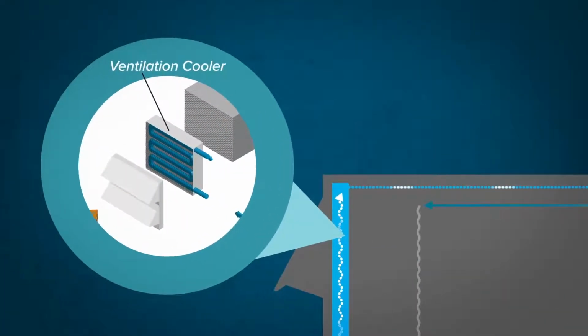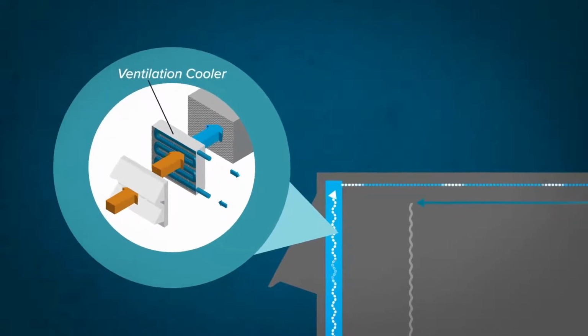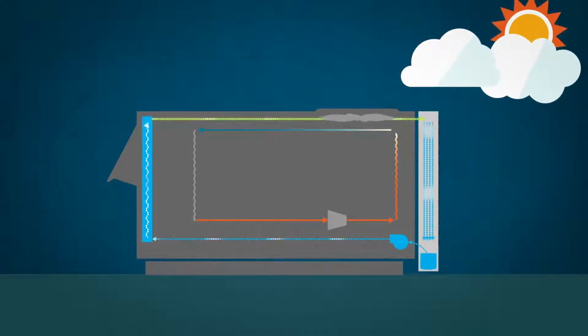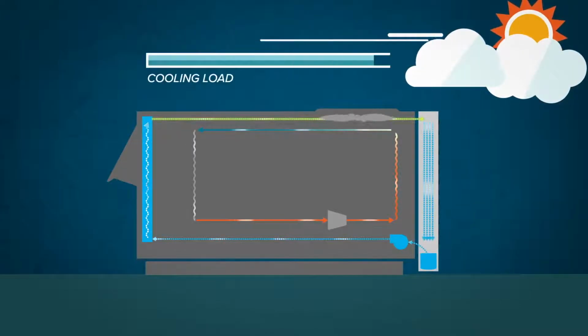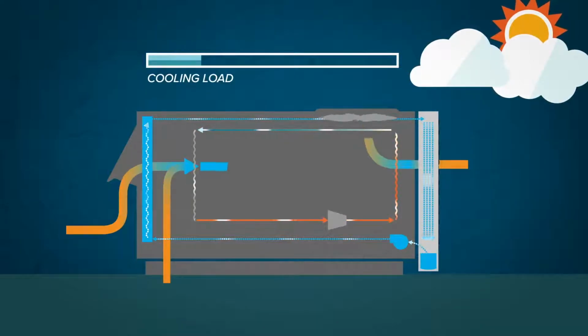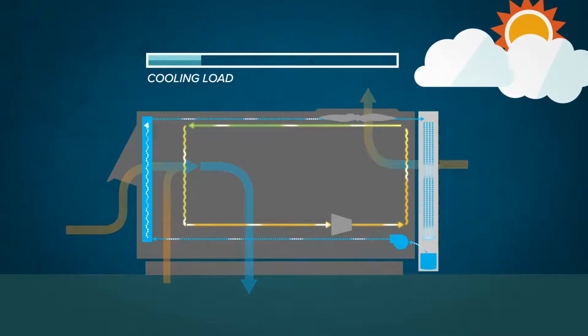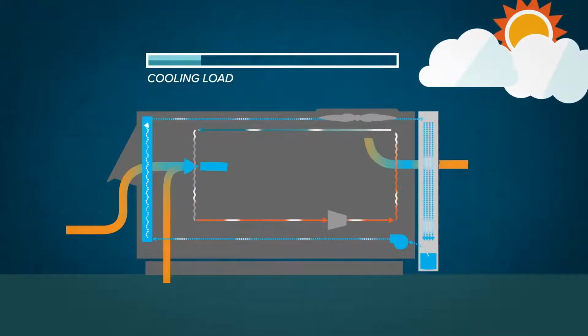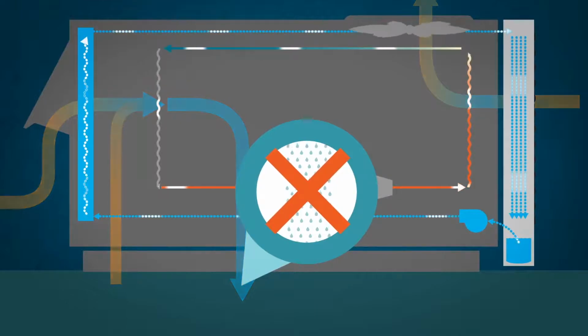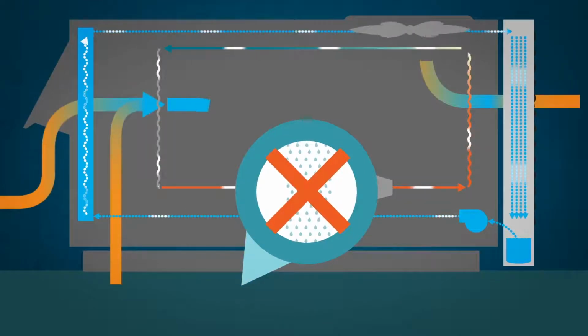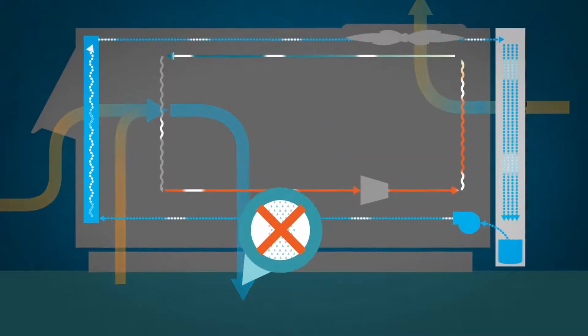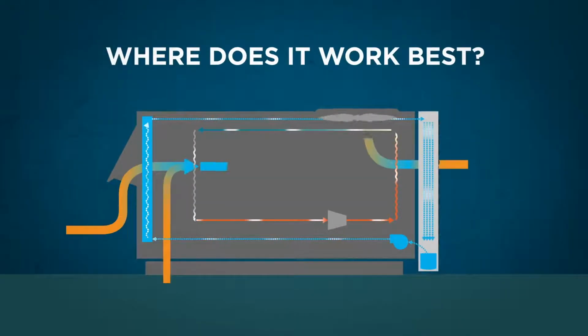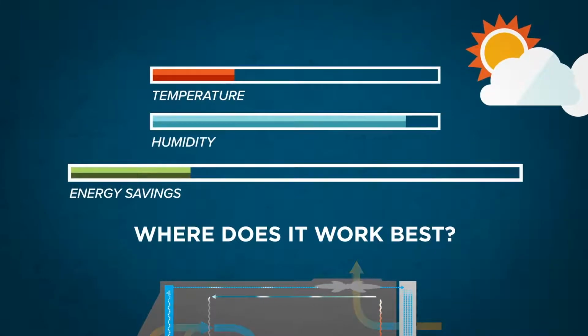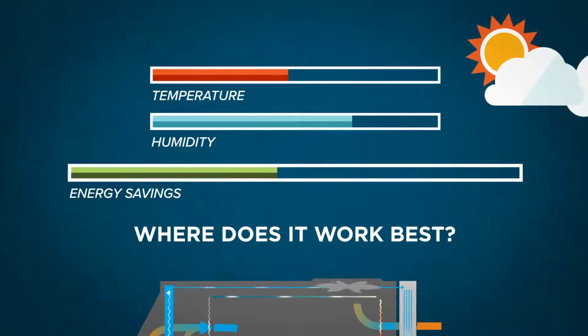This water circulates through a water-to-air heat exchanger, located in the ventilation airstream, which cools ventilation air before it enters the rooftop unit. The water is then returned to the evaporative media on the condenser side of the DualCool. In this way, DualCool simultaneously reduces the cooling load and improves the efficiency of the vapor compression cycle. Although evaporation is used to provide these benefits, no humidity is added to the air that then enters the building. The evaporated water is rejected outdoors by the condenser fan. DualCool is effective for a range of climates and applications, but the energy savings achieved increases as outdoor temperature increases and humidity decreases.